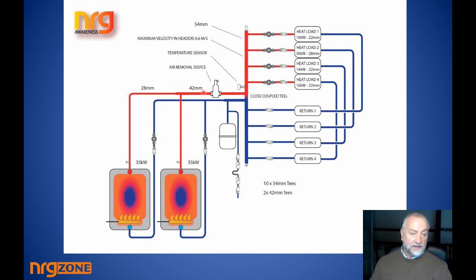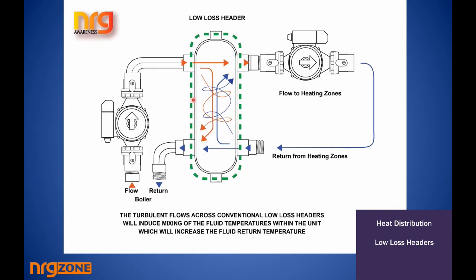So we're focusing at this point in time on the 54 mil header or 2 inch pipe header for 70 kilowatts. And when low loss headers were introduced, the first reason they were brought there is that at that time boilers were generally not condensing, heat pumps were not normal, and so the last thing you wanted was condensation temperatures heading back into the boiler that would cool the surfaces so much that they would affect the flue gases and cause them to condensate, where the condensation would be slightly acidic.